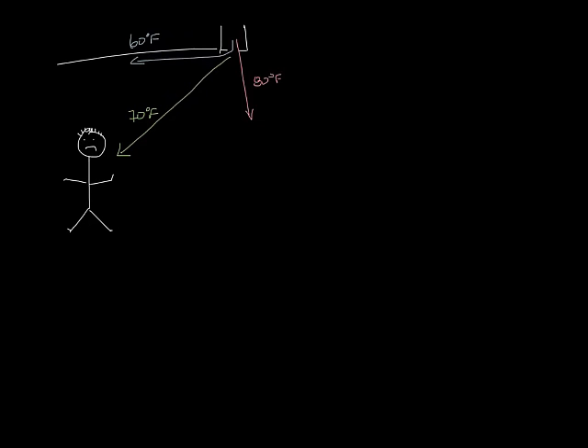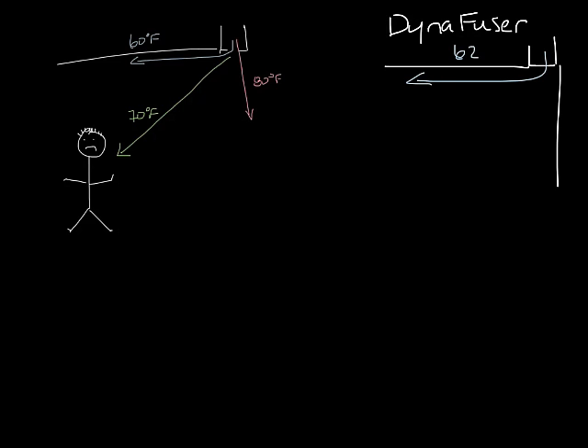The bimetal alloy that the Dynafuser uses snaps between the heating and cooling positions. So if the supply temperature is 55 degrees the unit will snap to the cooling position and stay there until it sees 82 degrees. Then it'll snap to the heating position and stay there until the supply air drops below 62 degrees again.